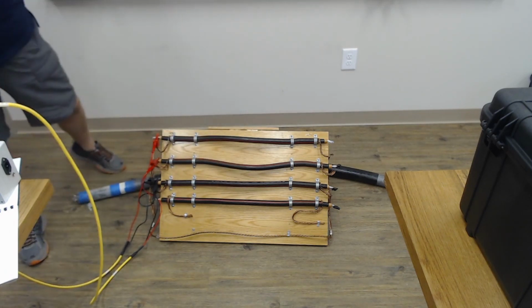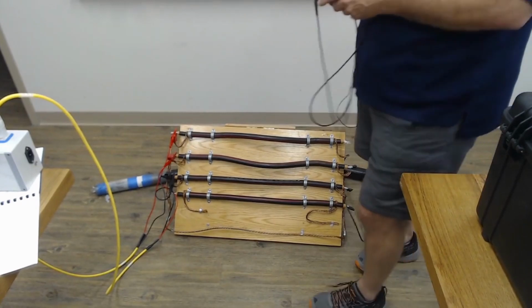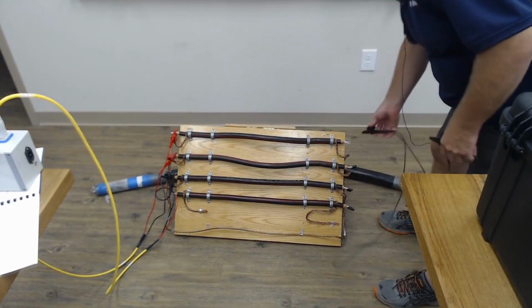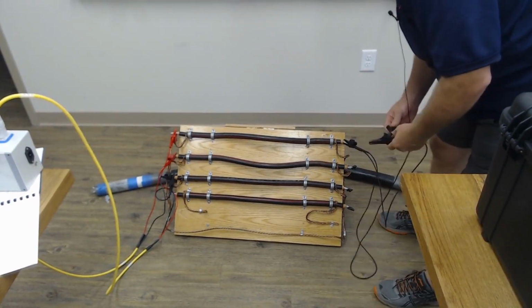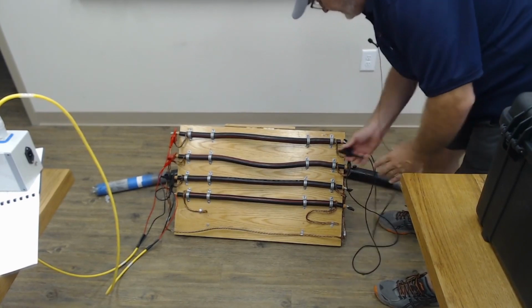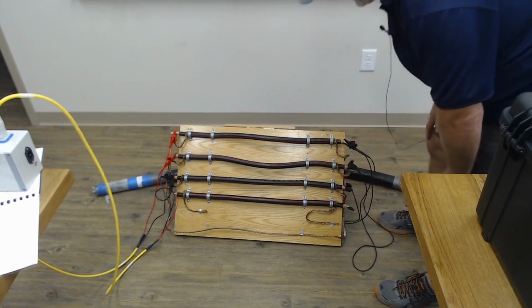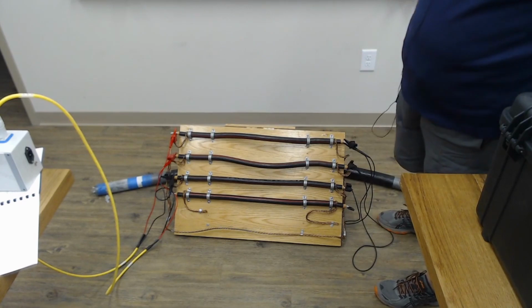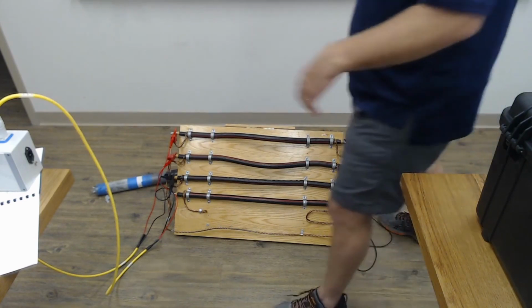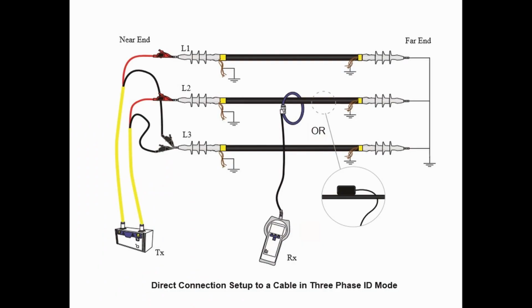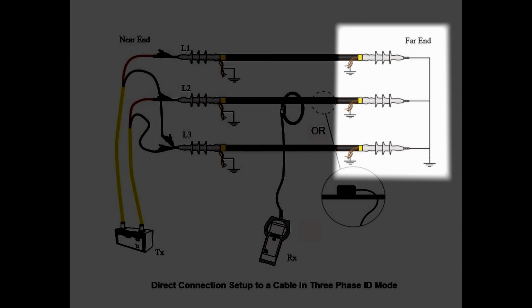Next thing, we need some jumpers on the far end. On the far end of the cable, we're just going to jumper all three cables together, A, B, and C phase, like that. You can ground the far end of the cable as well. So if you wouldn't mind bringing up the schematic of what we've just done, that's the direct injection. So that's exactly what we've got here. The far end of the cable is grounded. The near end is connected to AB and returns on C phase.